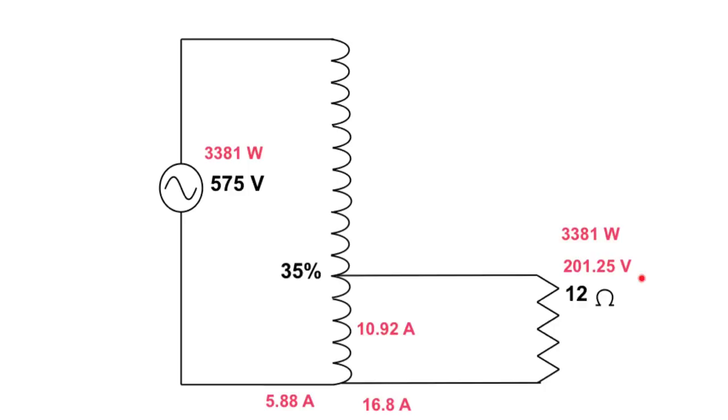Then I can take this voltage times this current to get this power. VA in is equal to VA out, so we can take that power and move it over to here. We take this power, which is the same, divided by that voltage to get that current. And then we take this current and that current, and we subtract them from each other to get the current across the common winding.